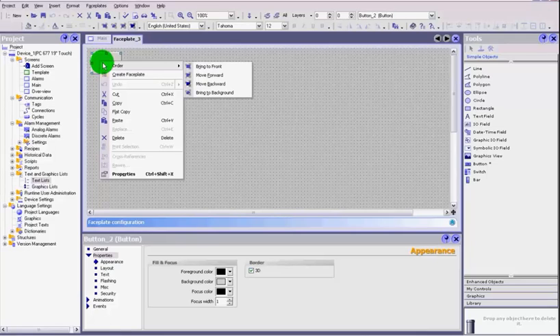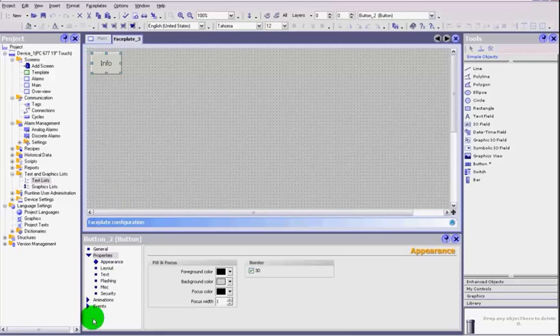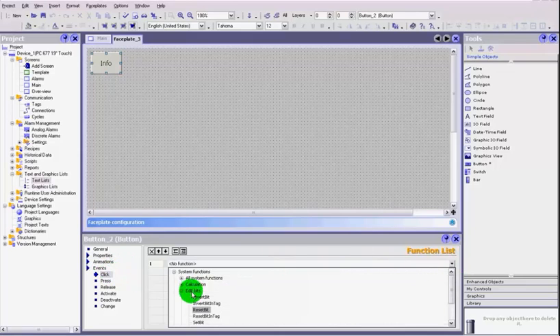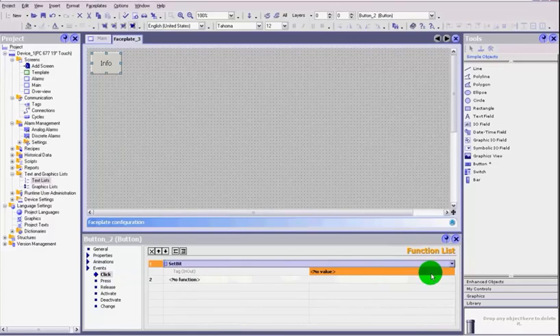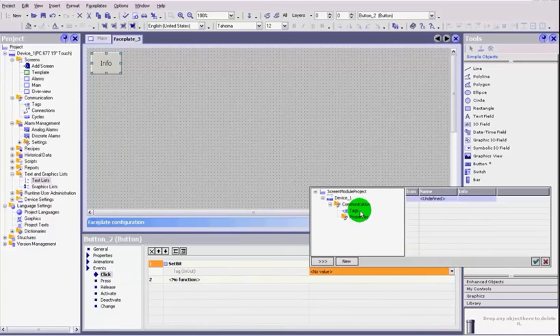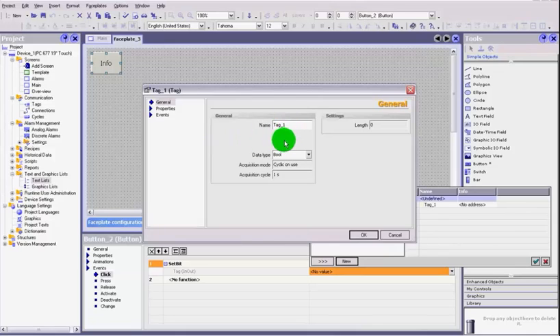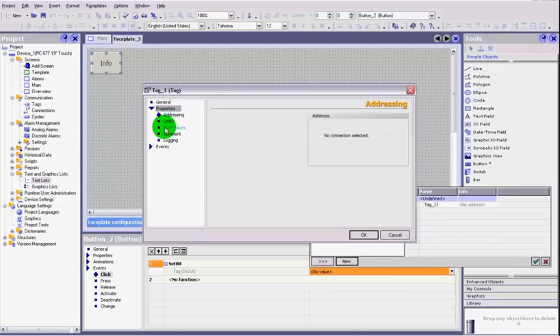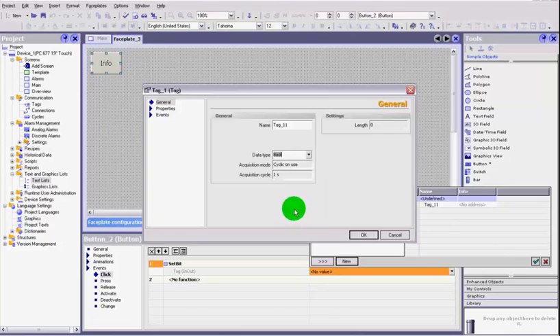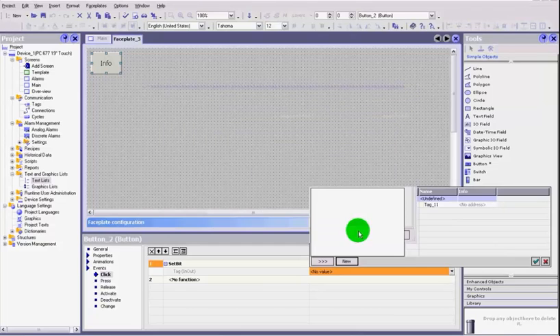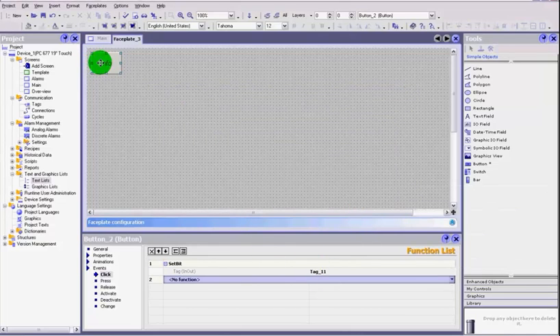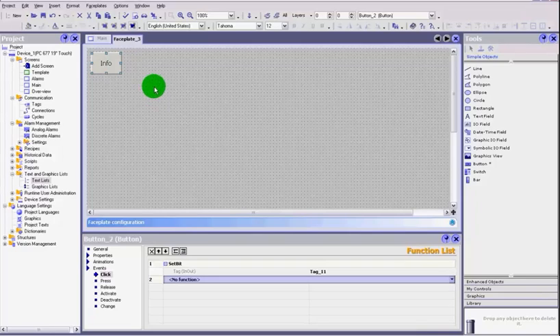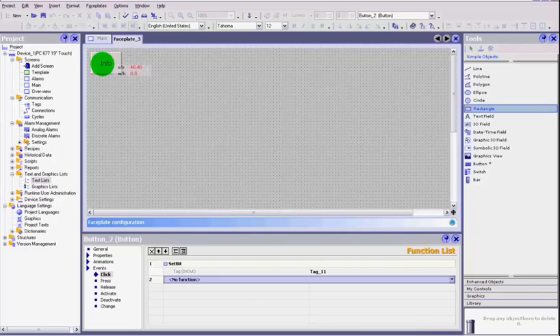What we need to do is first create a tag. We are going to create an event, so on click we are going to set a bit. I am going to create a new one, let's call it tag 11. We have done this before in previous videos. We just have to give it a tag and make sure that it is a boolean tag. We click ok, and now we have got a tag that we have set when that button is being pressed.